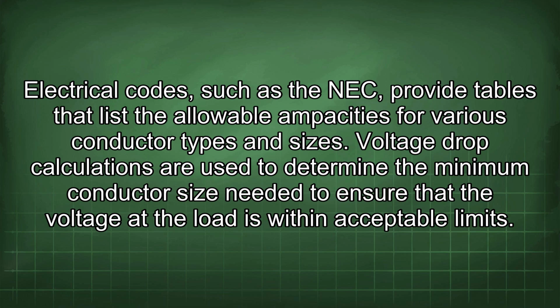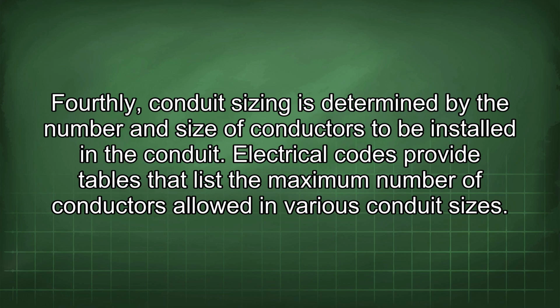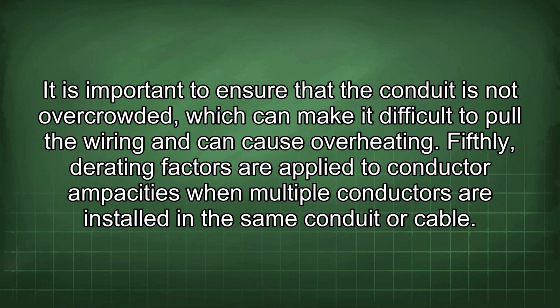Voltage drop calculations are used to determine the minimum conductor size needed to ensure that the voltage at the load is within acceptable limits. Fourthly, conduit sizing is determined by the number and size of conductors to be installed in the conduit. The electrical codes provide tables that list the maximum number of conductors allowed in various conduit sizes.